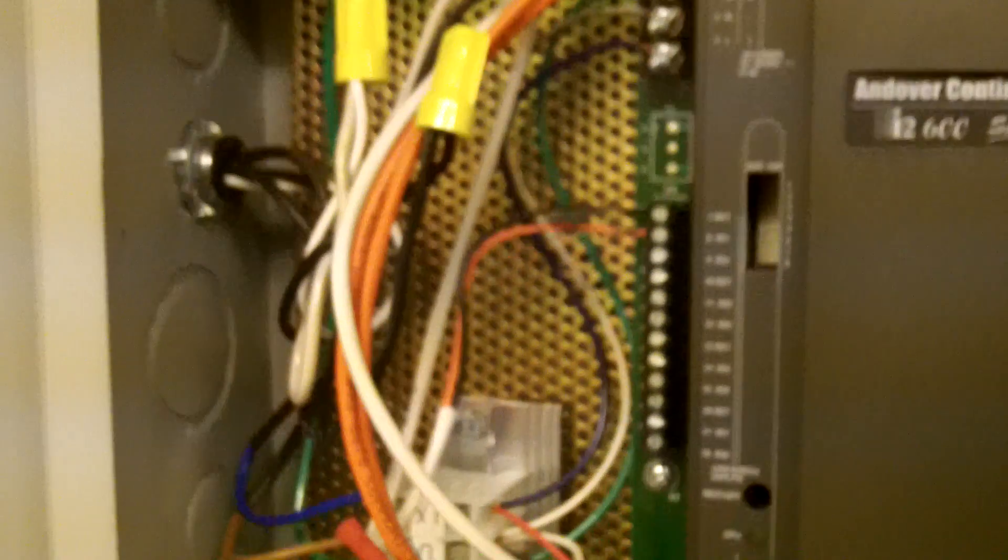Now this is a violation of section 800.133A1D. Communication cables like this are not permitted in the same enclosure with power conductors.